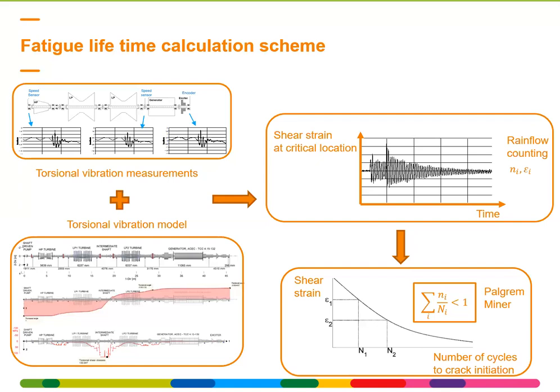When the shaft line is excited in torsional vibrations, you will excite it at different torsional eigenfrequencies. So you need dedicated bandpass filters at each of those frequencies, which tell you the correlation between a certain vibration amplitude and the stress experienced by the shaft. Once this is done, as you can see on the right, you will have a time plot figure, which shows you the shear strain you experience at a critical location. And then the standard-based rain flow counting technique, for instance, determines the number of cycles you have at a certain shear strain amplitude based on this time plot. This is typically rain flow counting. So this gives you the number of cycles and, for each cycle, what shear strain amplitude or shear stress amplitude you have experienced.